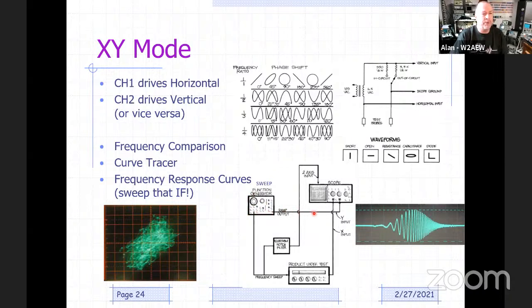Okay, I had the ramp output, the frequency ramp, go out to one input, and then look at, say, the voltage coming out of the IF transformer as I apply this sweep signal into the device I'm testing, and actually look at the frequency response as I go across. So that's a more sophisticated use for XY mode if you really like playing with scopes. There's better ways of doing this these days, but this is what XY mode is typically used for.